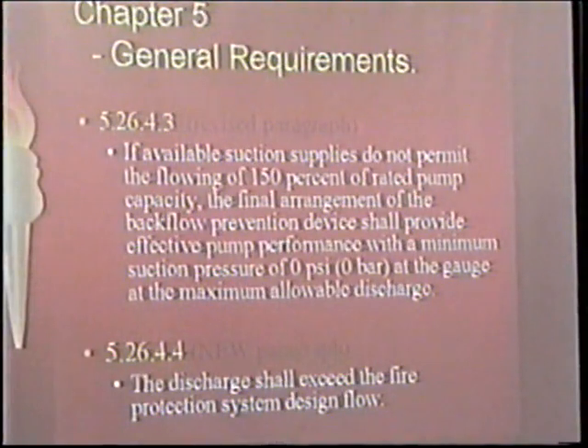What they changed here, we talked about this backflow device. In the previous paragraph it was very similar to this. However, what they're saying now is that if the suction supply does not permit 150% rated capacity of the pump, the backflow device has to be installed in a way that it can at least have zero pressure. And I'm not sure what they mean by effective pump performance, if that's rated capacity, if that's the sprinkler capacity. I think that's design requirement. That's the way I would interpret it.